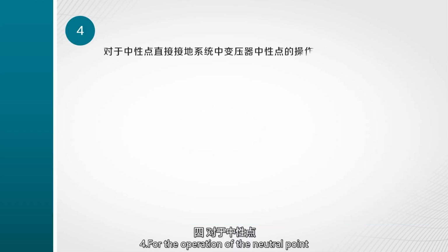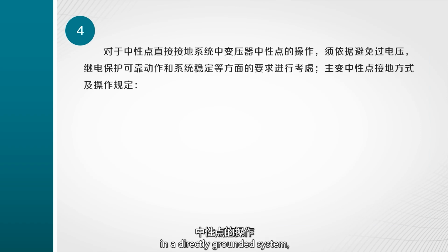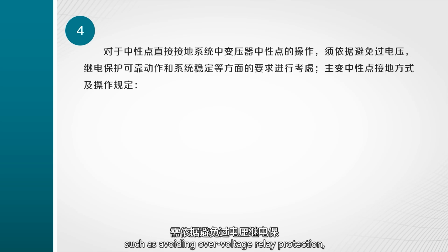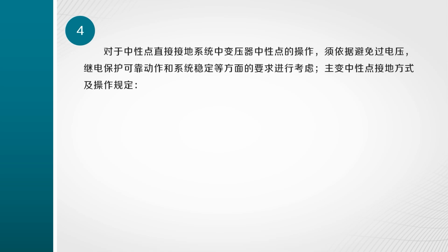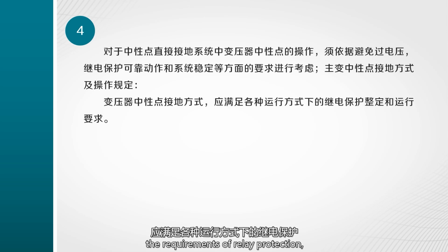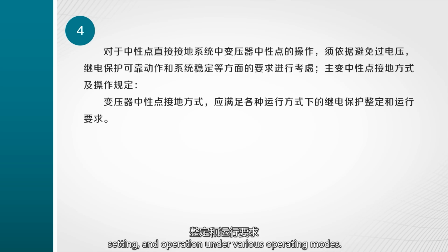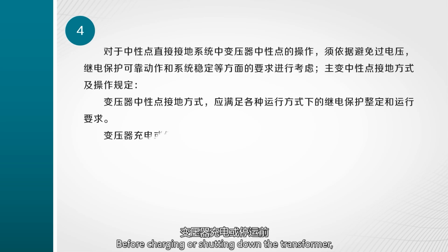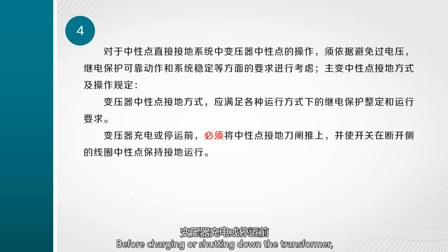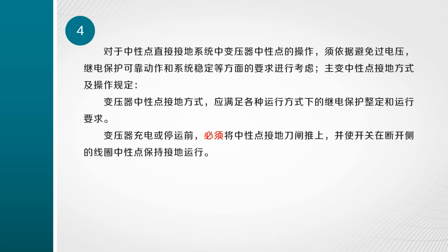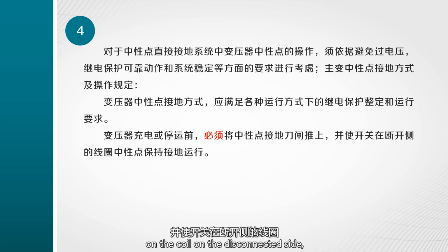Fourth, for the operation of the neutral point of a transformer in a directly grounded system, consideration should be given to requirements such as avoiding overvoltage, relay protection, reliable operation, and system stability. The grounding method and operating regulations for the neutral point of the main transformer should meet the requirements of relay protection, setting, and operation under various operating modes. Before charging or shutting down the transformer, the neutral grounding switch must be pushed up, and the switch must be placed on the coil on the disconnected side, with the neutral point remaining grounded.